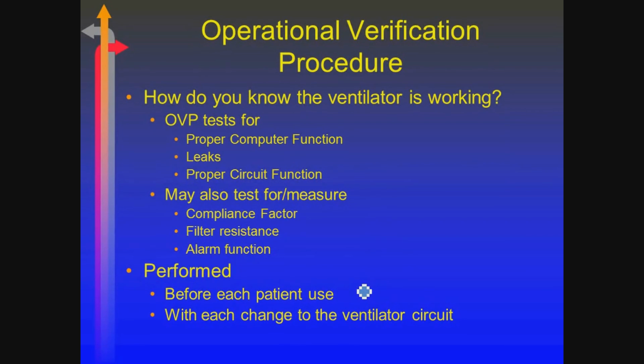3 days later, that ventilator is now needed. Then we go ahead and just pull it and assume, bad word, we assume, sorry Steve, that the operational verification procedure has been performed. Okay. On the 840 and on the Draeger, and I think on the Servo also, all three of them will tell you when the last one was done. So you kind of get an idea.